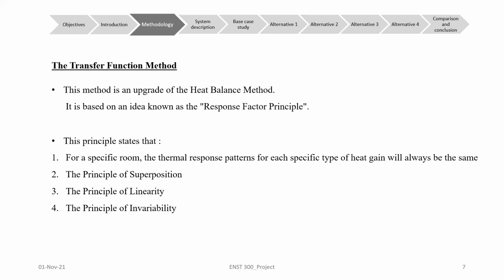This principle is based on three other principles. The principle of superposition, which states that the total room load is equal to the sum of the loads calculated separately for each heat gain component. The second is the principle of linearity, which states that the magnitude of the thermal response to a heat gain varies linearly with the size of the heat gain. The third one, the principle of invariability, states that two heat gains of equal size occurring at different times will produce the same thermal response in a room, as I gave in the example of 1000 and 2000 BTU per hour heat gain. Next slide.